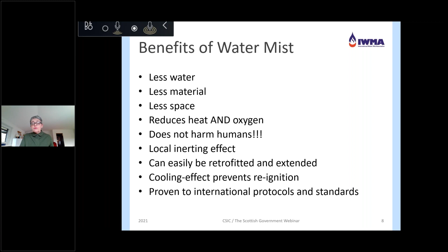When it comes to smoke control, water mist will efficiently cool the smoke layer, preventing the hot gas layer from contributing to further fire spread. It will also clean out some of the smoke particles. The technology is proven to international standards and guidelines, and is therefore ready to use.